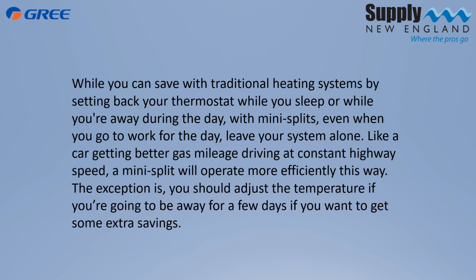Well, it's true on a traditional system that you can save money by setting back your thermostats. It is not true on a mini split, and we have to make sure they know that. We want it to set it and forget it, or cruise control. Those are 2 terms that you should get used to and use with your homeowners. We all know that we get better gas mileage when you're using cruise control. Now, the exception to this rule, because there's always an exception, is when they're going to be gone for a few days, that's when they can change that thermostat by a few degrees.